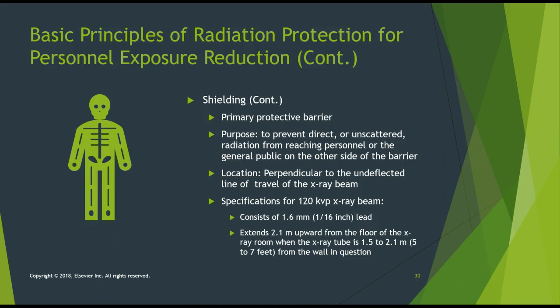Okay, there are two different types of shielding, primary and secondary. The primary protective barrier is the barrier that the direct beam is hitting. Its purpose is to prevent that direct or unscattered radiation beam from reaching personnel or the general public on the other side. So, for instance, the wall behind the wall bucky. Okay, so that's a primary barrier. Its location is perpendicular to the undeflected line of travel of the X-ray beam. So the X-ray beam is perpendicular to this main protective barrier.